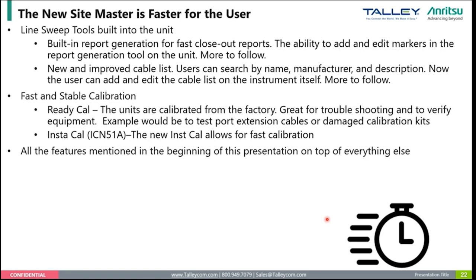A lot of times when people are out in the field, they would traditionally have two calibration kits: one known as a golden calibration kit, kept nicely protected in a box, and one they carry around, which sometimes gets damaged. We try our best to make it ruggedized, but it still gets damaged. At that point, some users might use the golden calibration kit to see how the measurement is and check if the other calibration kit is broken.